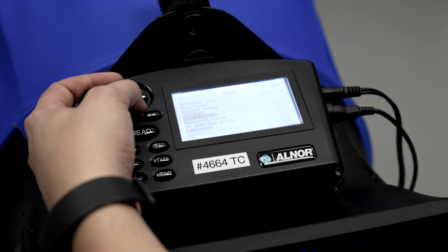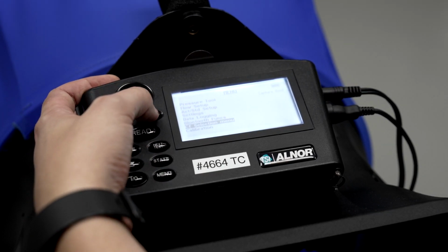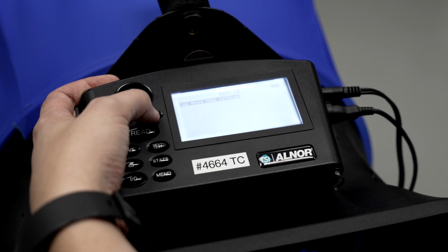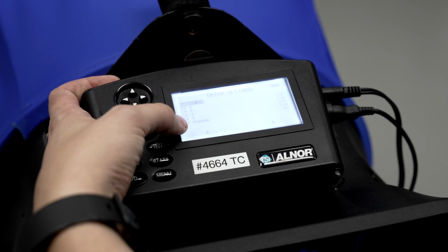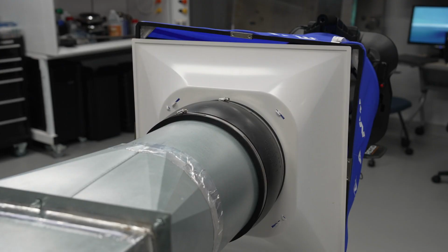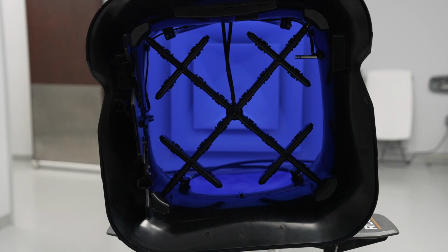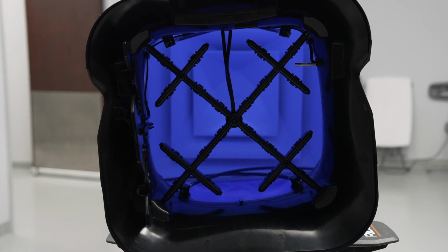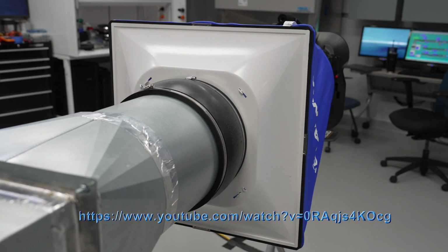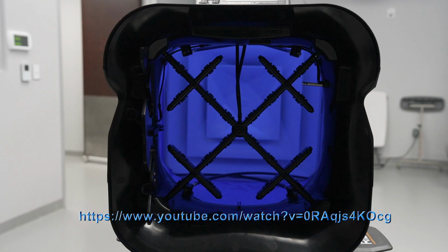This required a K-factor adjustment to both the SAV with the 11% calibration curve offset and the capture flow hood using a duct traverse method. This testing shows the importance of proper balancing done by trained and certified technicians. Capture flow hoods must be properly calibrated to the job site conditions using a traverse method, or else the entire system may be out of balance. For proper traverse calibration procedure, please reference the traverse balancing video produced by Engineered Air Balance at the link below, or go to their YouTube channel.